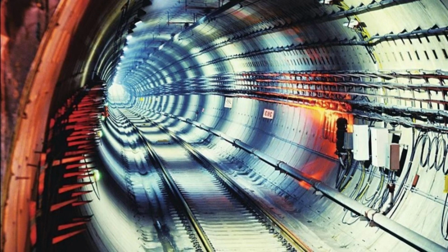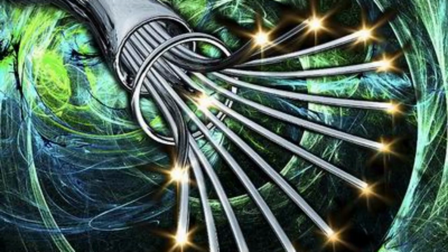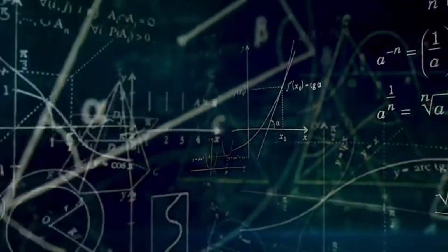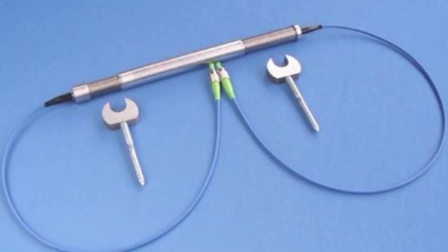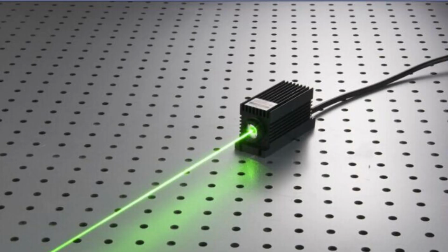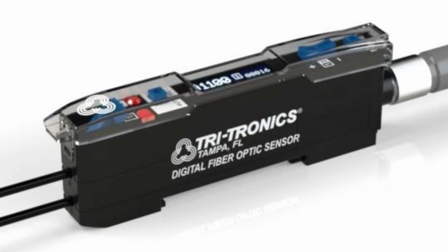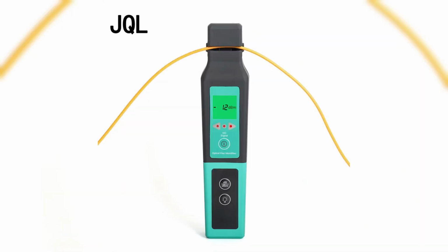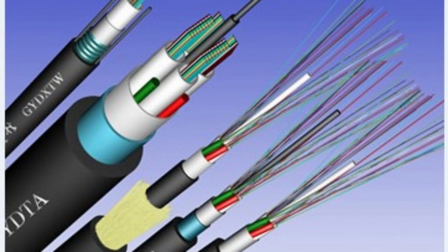Fiber optic sensing. Fiber optic sensing uses the physical properties of light as it travels along a fiber to detect changes in temperature, strain, and other parameters. Fiber optic sensing utilizes the fiber as the sensor to create thousands of continuous sensor points along the fiber. This is called distributed fiber optic sensing using a distributed fiber optic sensor. The devices measuring the fiber itself are generally called interrogators.